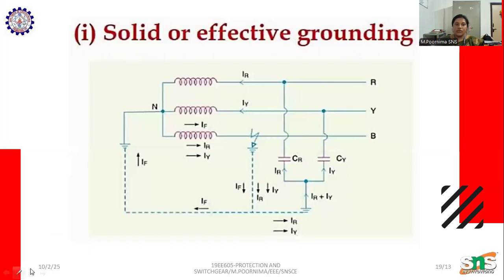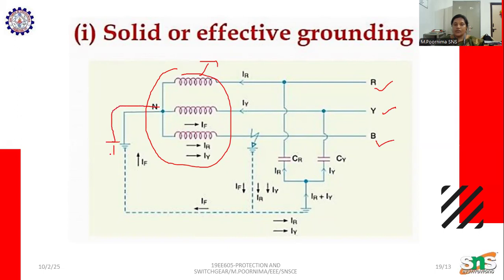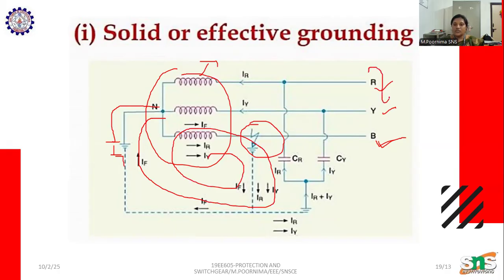Here we can see solid or effective grounding. Here we can see a star connected system, and we have R phase, Y phase, B phase, and we have the neutral. So the neutral is directly grounded. Here, if a fault occurs in the B phase, what happens? The fault current flows through this path, and the other two phases are safe. This is solid or effective grounding.